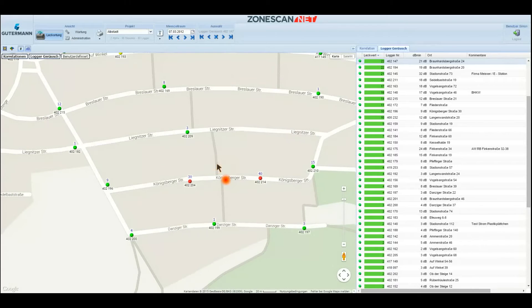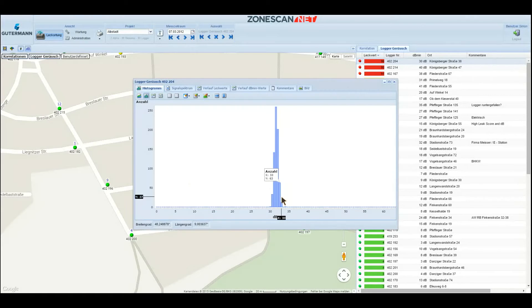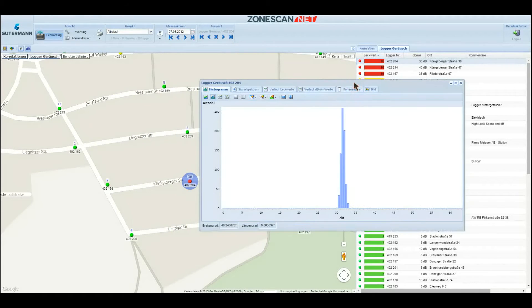As you can see, the loggers are red, which indicates a high probability of a leak being present. The system evaluates different measurement parameters. We are now looking into a logger. You get additional information in this window, one of which being the histogram, meaning the amplitude distribution.